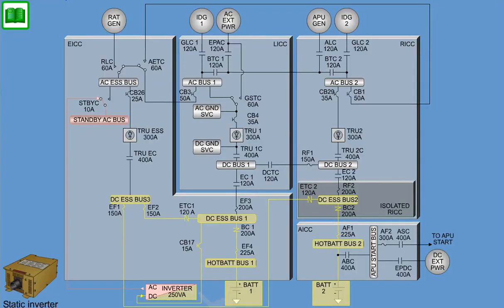During operation, the static inverter is powered by DC Essential Bus 1. In case power is not available to the AC Essential Bus, then the standby contactor inside the EICC will be de-energized, connecting and supplying the AC output of the inverter to the standby AC bus.